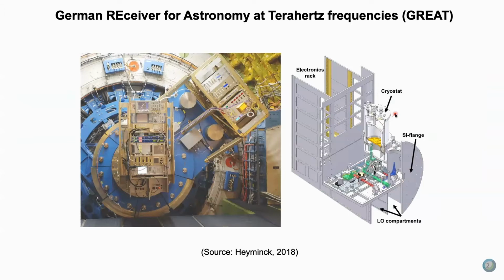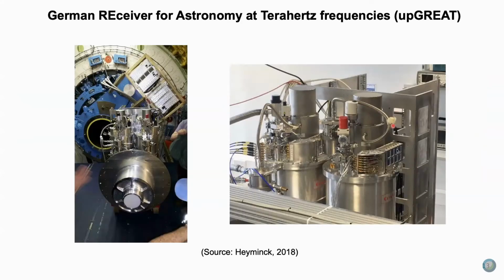So instead of liquid helium, what's used is a pulse tube refrigerator. Just a commercially available pulse tube refrigerator, 2-stage. And the second stage gets down to 4 Kelvin. So without using liquid helium, you're getting the detector down to 4 Kelvin. And it's pretty much just a plug and play cryostat at that point.